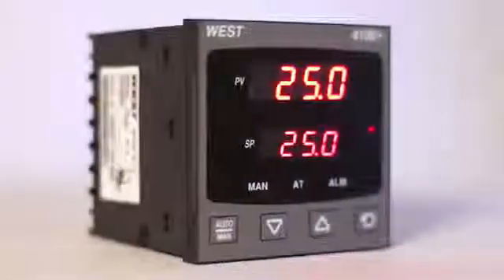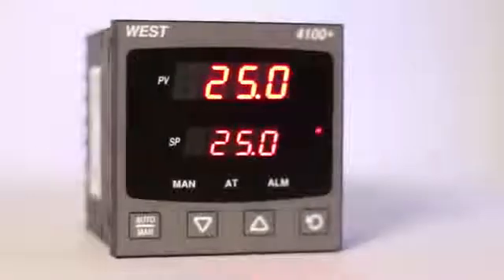The user has very little control over this except to adjust an on-off differential or hysteresis parameter if available. The on-off switching differential is the distance between the on point and the off point as the process crosses the setpoint. It is at least one least significant digit wide, which is normally either 0.1 of a degree or 1 degree, but can be adjusted to a wider amount if appropriate.